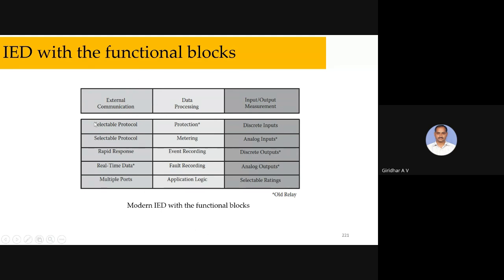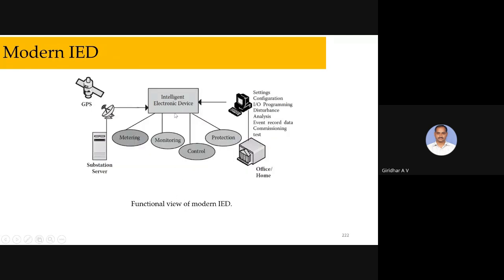whole functional blocks. Basically, with programming, different features of relaying operations can be done. That feature will be used in these IEDs as multifunctional relays. That is the main advantage if you go for these IEDs. We can have all different features, even event recording, fault recording, monitoring, protection, and control.